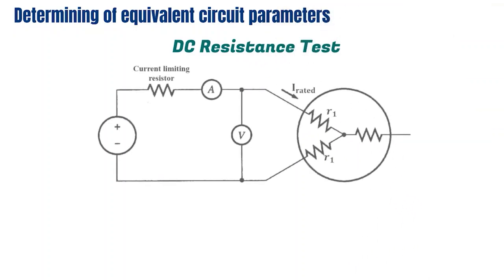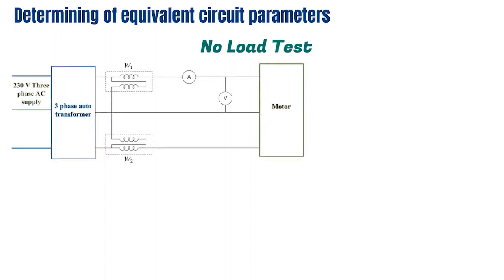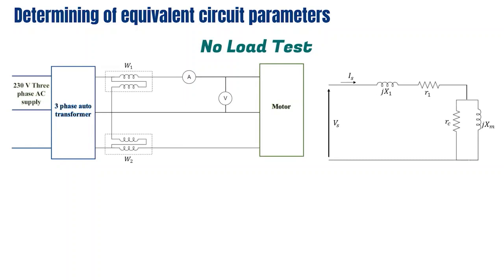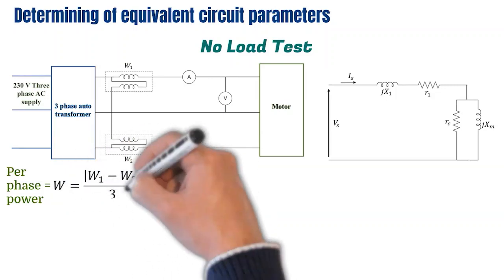Under the determination of equivalent circuit parameters, the first test is the DC resistance test. You can see the circuit arrangement on screen; the stator resistance R1 can be obtained using readings of a DC voltmeter and ammeter. Next is the no-load test, which is similar to the open circuit test in a transformer. The motor is allowed to rotate freely without a load by applying rated voltage at rated frequency. Since the rotor rotates without a mechanical load, the equivalent circuit is simplified, and two wattmeters are used to measure power. The per-phase power can be obtained as follows.